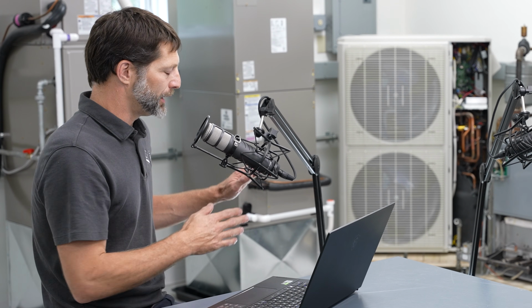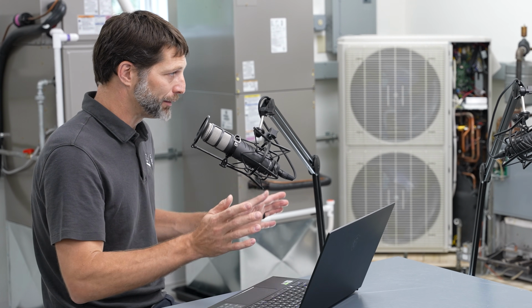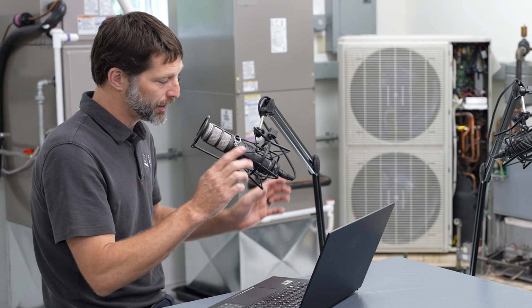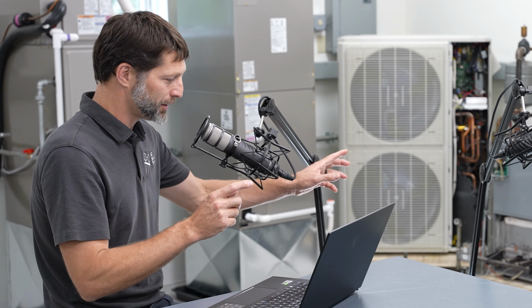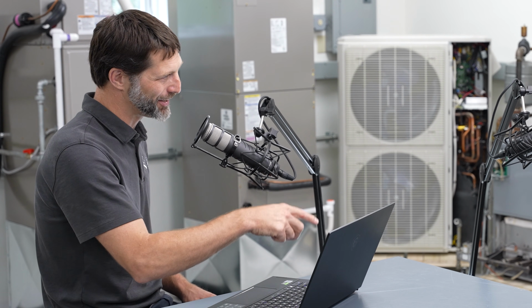Yeah, so the R22, R410A, like if it's below 200 pounds presently, if you can pull it down to 0 PSI, that's correct. But what a lot of people think is that they pull it down to, say, 0 PSI, and then they're good, and that's it. Well, the problem is, once you shut the recovery machine off, and it has a check valve. So some that don't have a check valve, you're going to have to shut the tank off first, then turn the machine off, and then check the pressure to see it rise.